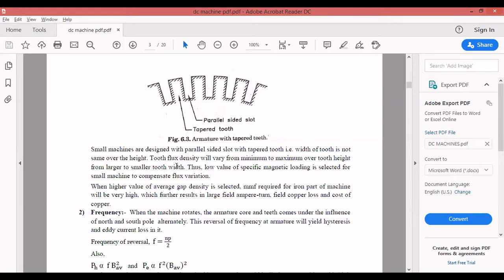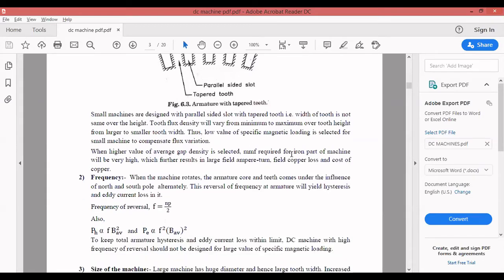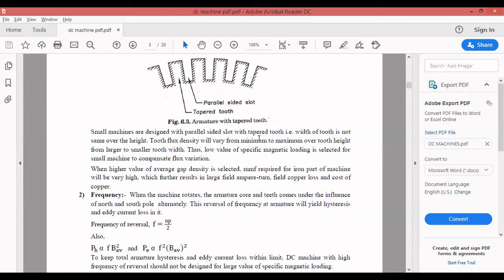The third factor is size of the machine. A large machine has a larger diameter and hence larger tooth width. Increased tooth width permits a higher value of gap flux density without causing saturation. The usual value of gap flux density B_g is 0.55 to 1.15 Wb/m², and average gap flux density B_av is 0.4 to 0.8 Wb/m².